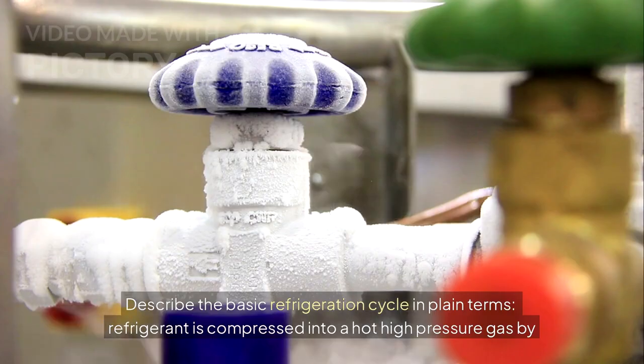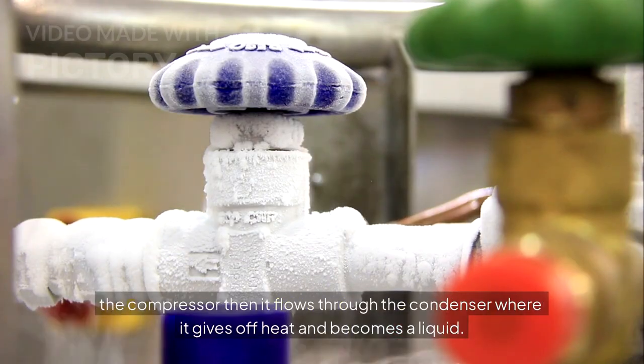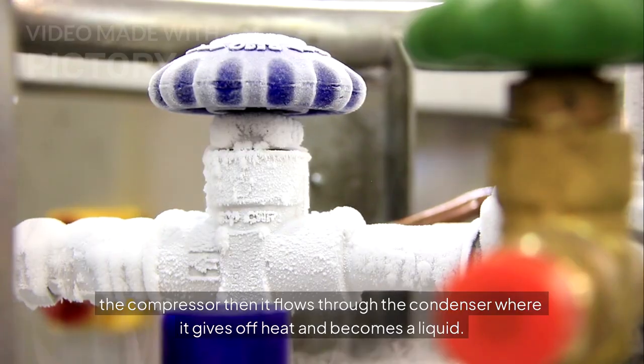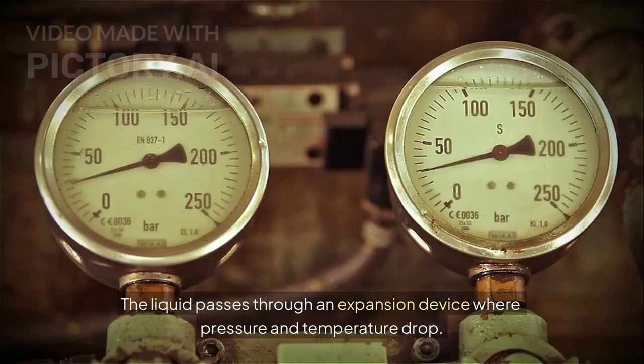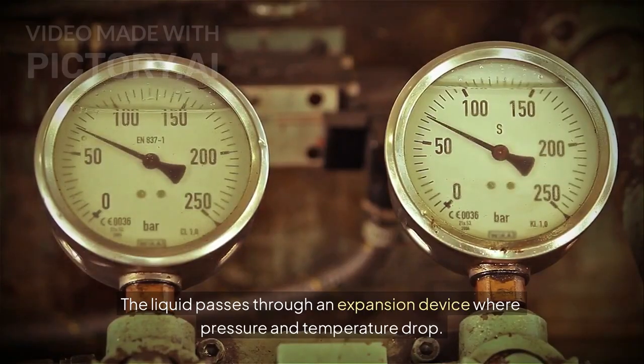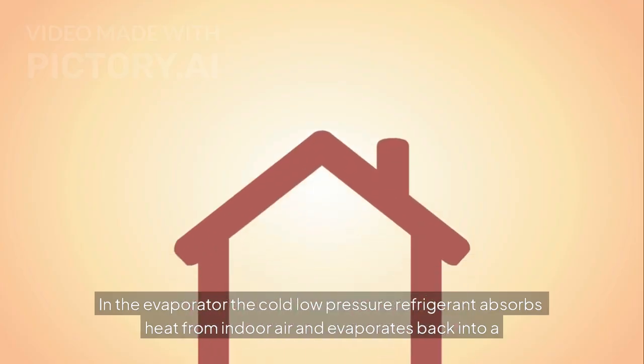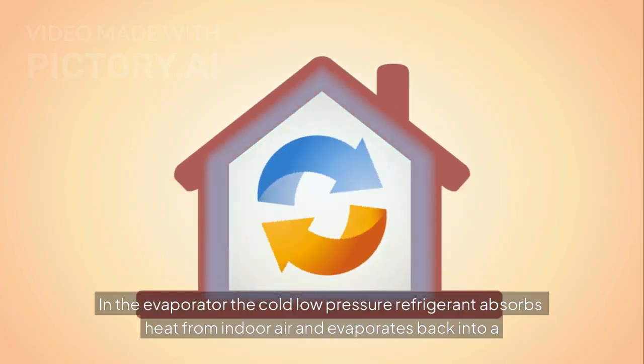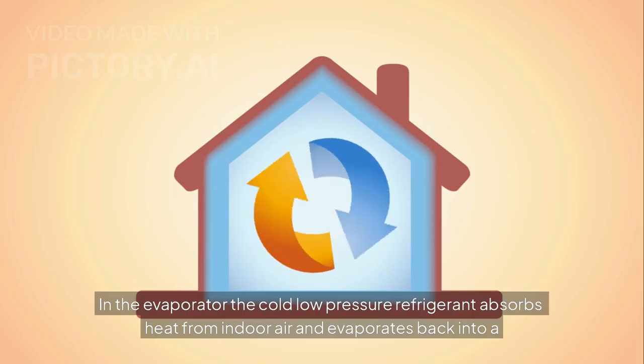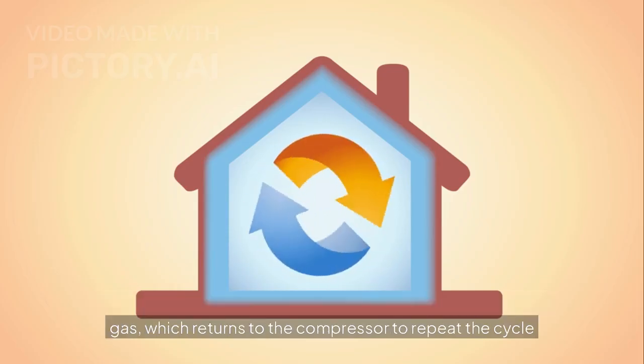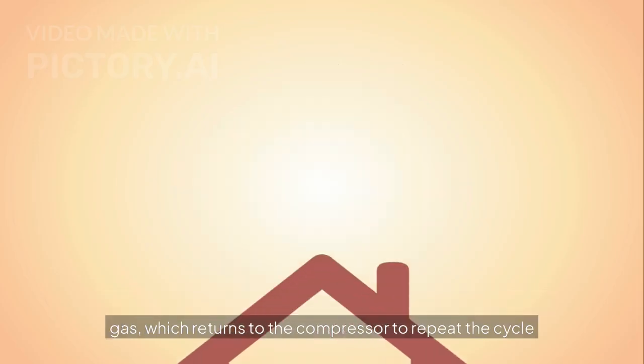Refrigerant is compressed into a hot high-pressure gas by the compressor, then it flows through the condenser where it gives off heat and becomes a liquid. The liquid passes through an expansion device where pressure and temperature drop. In the evaporator, the cold low-pressure refrigerant absorbs heat from indoor air and evaporates back into a gas, which returns to the compressor to repeat the cycle.